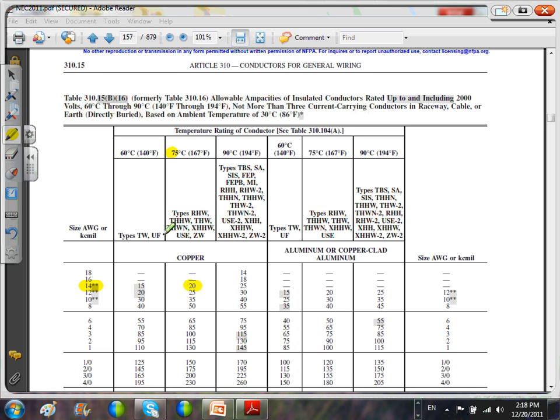Take a 100 horsepower motor. The reason I'm not saying horsepower, guys, I'm giving amps is because of ease of calculation. Let's take a 100 amp motor. I know they're rated in horsepower, but I'm using the amps just for the ease of calculation. 100 amp multiplied by 1.25 will give you 125. So I'm going to size a cable for 125 amp, 130, perfect. Then I need 3 conductors. Number 1, done. This is one of the most important tables that you guys are going to be encountering. No question asked. Any comments, guys, about this?